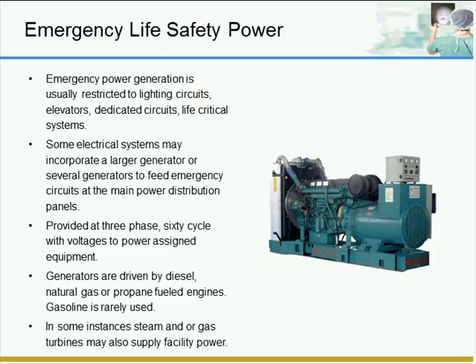Emergency generators, the life safety power. Emergency power generation typically supplies power to lighting circuits, elevators, dedicated circuits, and life critical systems. Some electrical systems may incorporate a large generator or a few smaller generators. The life critical generators will typically supply three-phase 60 cycle power, typically at 480 volt or less. Generators are typically run off diesel, natural gas, or propane. Again, you might have an emergency backup power supply, which involves a steam or gas turbine as well.